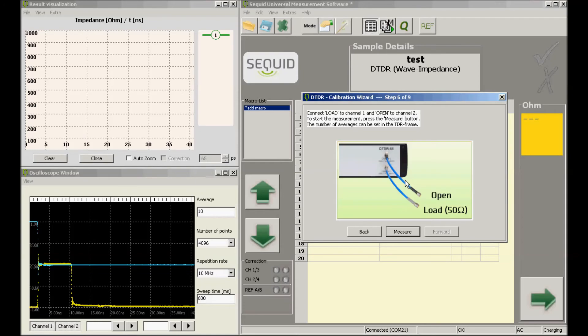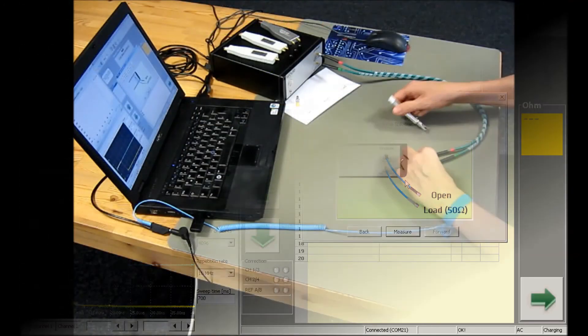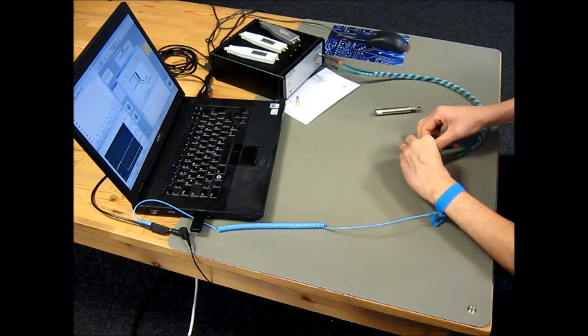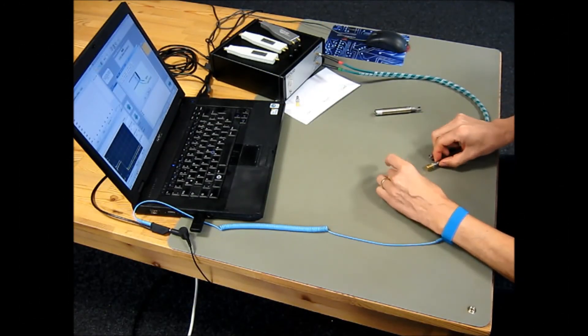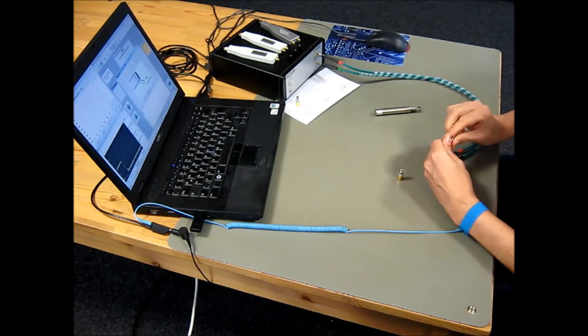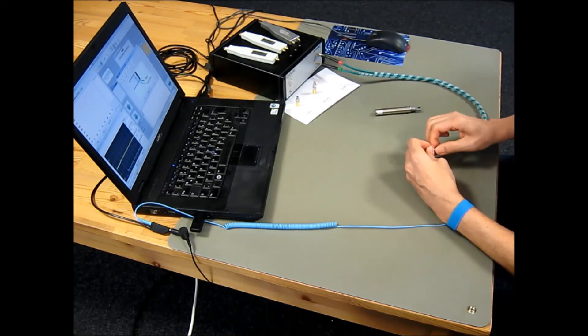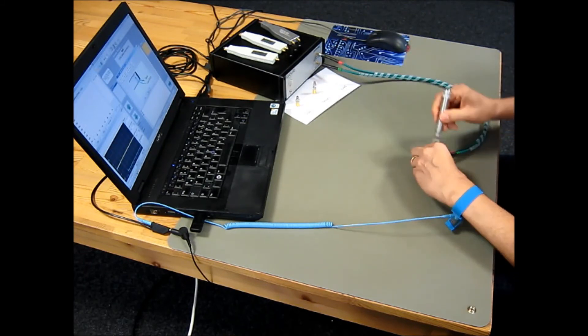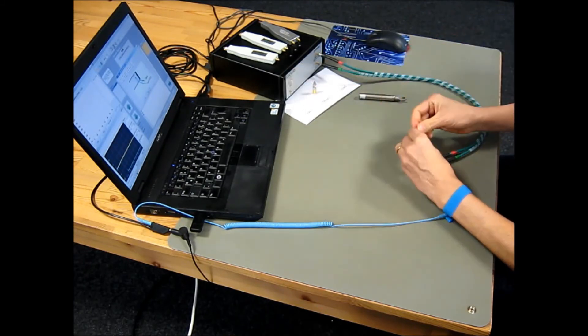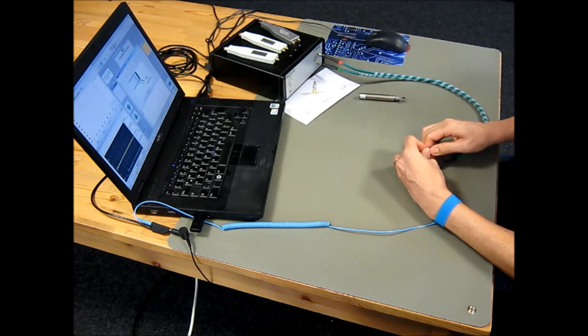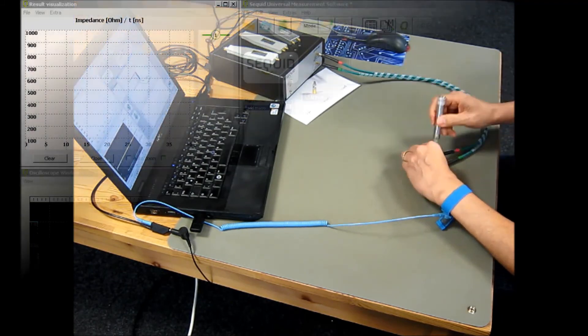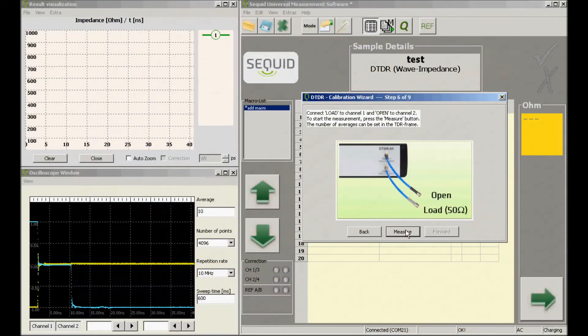For the last change of calibration standards we speed up the video a little. Channel 1 is now the flat line, and channel 2 is reflected in the same direction as the incident step due to the open.